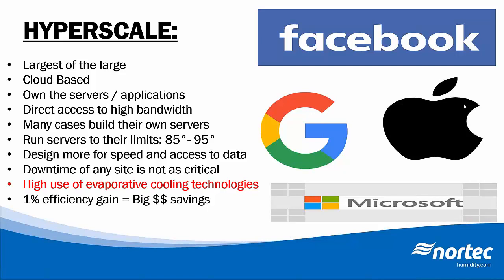That being the case, they're willing to risk their servers more. So you'll see them running at return air temperatures as high as 95 degrees and supply air temperatures up in the 80s. They will not have the requirements for such tight humidity control. They're not as worried about contaminants coming into their environment, so they'll use some filtration of outside air. And again, the reason for that is that they're building more for efficiency than they are for reliability. If you think about a 10 megawatt data center, for instance, if you can get 1 or 2 points of efficiency gain, think about the electrical energy savings that you have there. So their methods of building these sites are quite different than we're going to talk about when we get into the co-location and the enterprise.